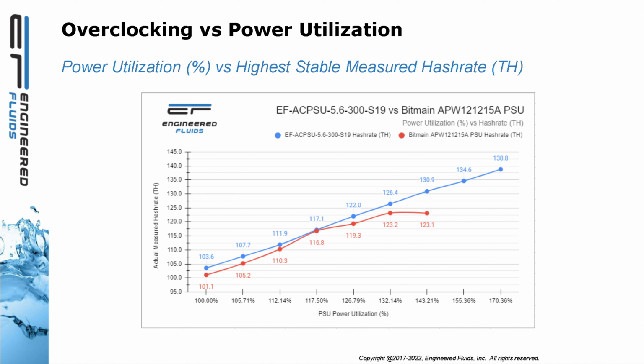This is probably the biggest design flaw that I see in so many of our immersion systems, with our competitors and folks that have no experience. They underestimate the inefficiency of the power supplies, and they underestimate the fact that that inefficiency creates more heat. And if you don't account for that in your system, you're going to end up with a system that is inefficient and ineffective and incapable of meeting the financial model that you sold your investors.